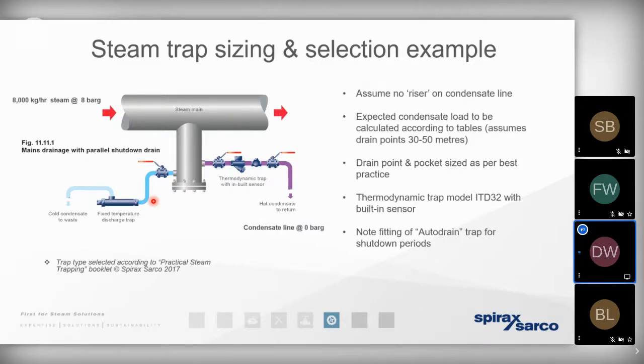Essentially, it works thermostatically. So whenever the steam system is switched off, any condensate that is languishing there at a very, very low temperature can drain to waste under gravity. That condensate doesn't have any value to us. It's low temperature, and if it's left there, it can cause more problems with erosion, corrosion, and water hammer. So if that were the case, we wouldn't need to allow for the warming up load for this particular type of valve. That excess mass of condensate that was generated when the system was warming up, and therefore at a low temperature, would be dumped to waste by the secondary trap. We could have that occurring on some systems.